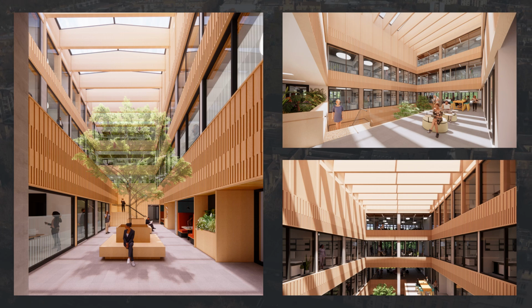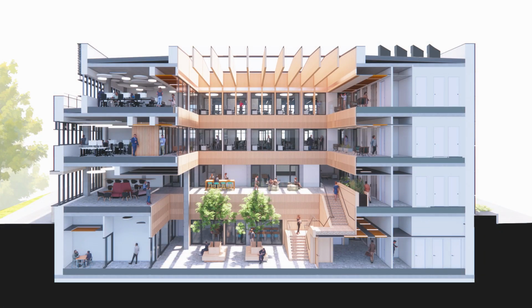In this case, we've also used the atrium as something we call a solar reservoir. The idea being that in the winter, through the use of our solar gains and the return air from the spaces in the building, warm air would collect at the top of the atrium, and we would extract that warm air back to our air handling units and through heat recovery, recover the heat and reintroduce it into the building. We find that this works pretty well. We've used it on other projects, for example the medical sciences building at the University of Leicester, and it helps drive the efficiency of the building even further.